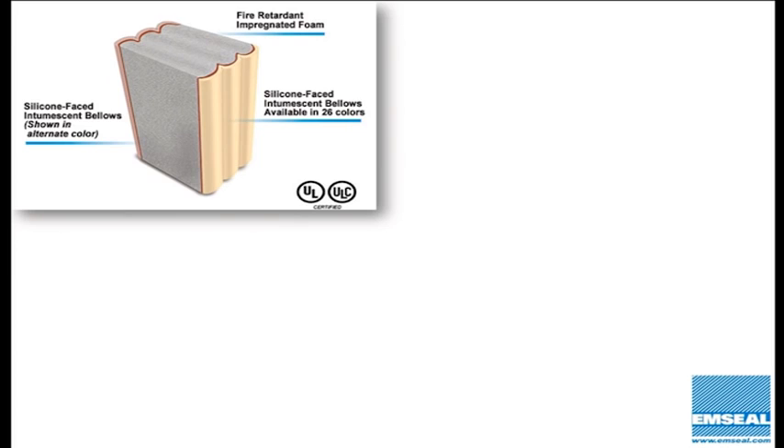This was done conservatively to benefit from our first investments in UL testing — each time we go back to UL we're spending tens of thousands of dollars. But the test results from our early testing showed that temperature values on the backside of the product were so far below the pass requirements for UL 2079 that we knew we could eventually iterate beyond the requirement for intumescent.